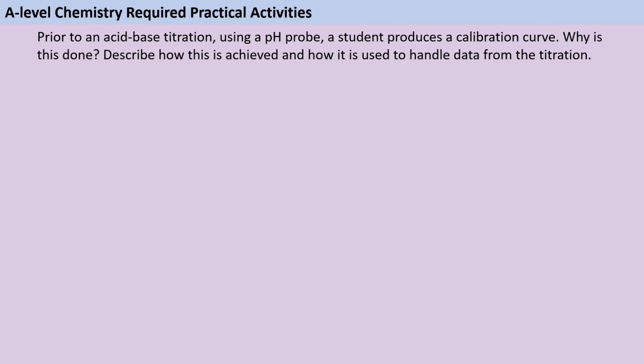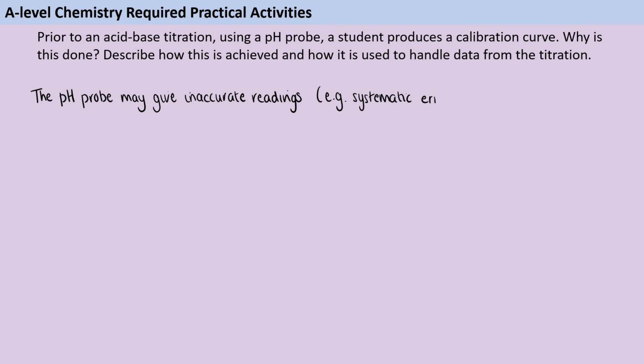So the reason that we produce a calibration curve is that it's very common for pH probes to give slightly inaccurate readings. Now that could be a systematic error, so that could mean that your pH meter is always saying a value that is 0.1 higher than it should be, for instance, or it could be slightly different in different parts of the range. So it may be that it reports high pHs as being too high and low pHs as too low. And whichever one of these issues we encounter, a calibration curve can help us because it allows us to adjust the readings that we're getting from the pH probe to actually reflect the accurate pH of that solution.